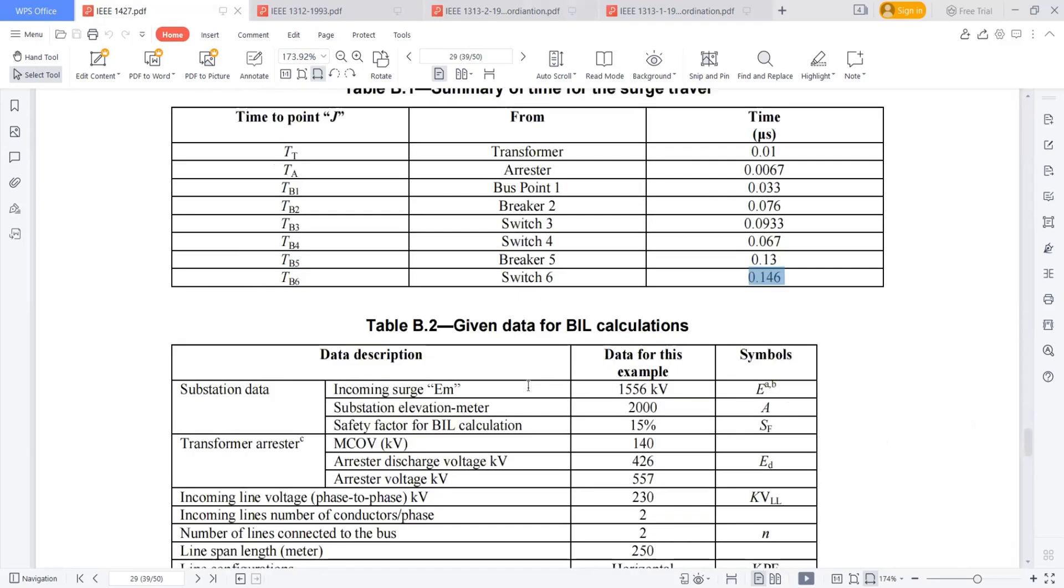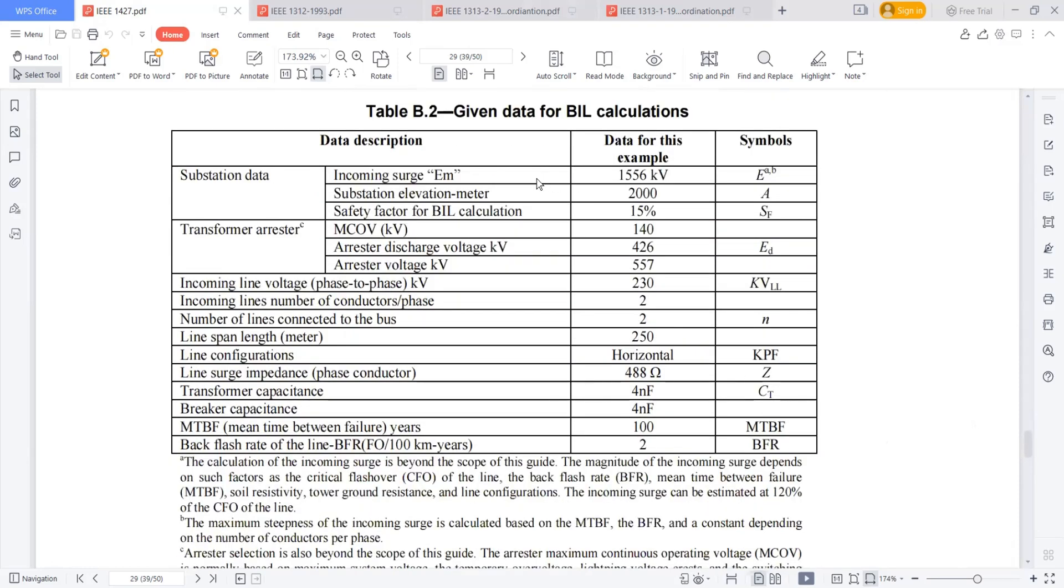Next I am collecting some data for doing this calculation. What is the data required? The first one is I need to know what is the incoming surge I can expect in my substation. How this depends is it depends upon the critical flashover rate of your transmission line or back flash rate of the transmission line. Generally, the incoming surge as per IEEE 1313 part two, it was mentioned that 120% of the critical flashover of the line gives you the incoming surge.